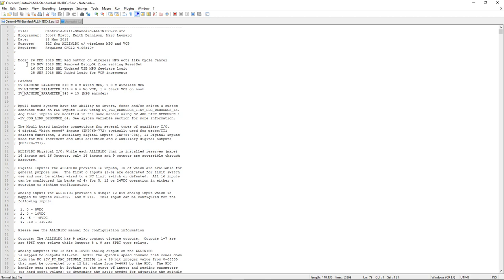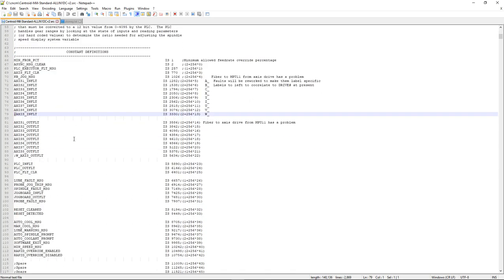Another thing Centroid does is include a section that logs any modifications made to the PLC program: the date it was done, who did it, and what exactly was changed. This allows anyone in the future to easily troubleshoot. You can also add variables, parameters, macros, custom M codes, or auxiliary buttons to the header, giving it a one-stop shop so someone can open it up and immediately see, for example, which aux button controls the vacuum pump.